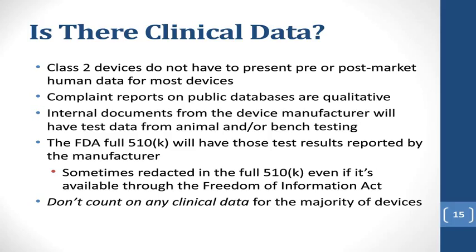These are all things that you would want to look for in the documentation, because the manufacturers of these products, Olympus is a huge company, and it's not as though they haven't done any risk analysis. If you get to the point where you look at any of their internal documents, I'm sure there are going to be pages and pages where they've done electrochemical testing, where they've done physical strength of materials testing, where they've even tested, the lawsuit alleges, the cleaning protocols, but they just didn't update them when the design changed.